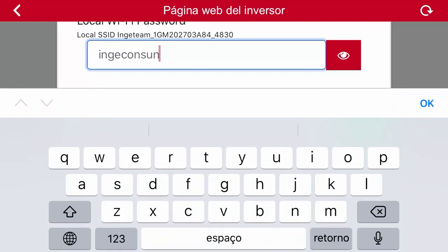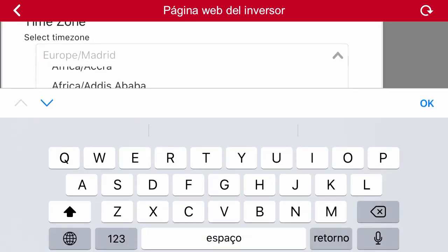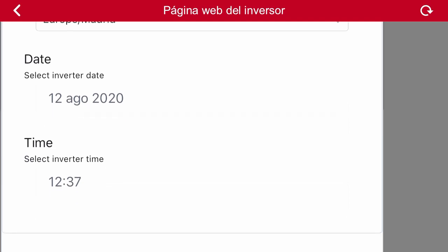The next step in the commissioning is the communication setup. The first suggestion the application makes is to secure the inverter's Wi-Fi network. To do so, we must select a password for the unit. Ingeteam recommends the use of 'ingecon-sun' as a password, although installers could change it and select any other one. The next parameter is the configuration of the date, time, time zone, and the location where the inverter is going to be installed. By default, it will take that information from the smartphone.